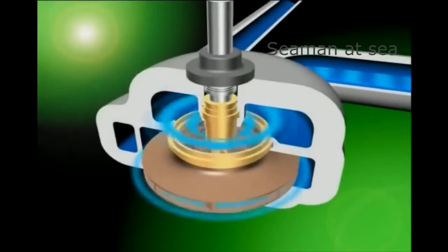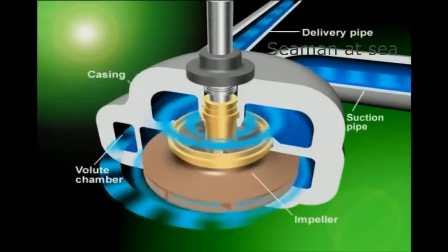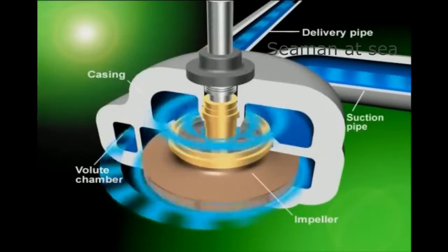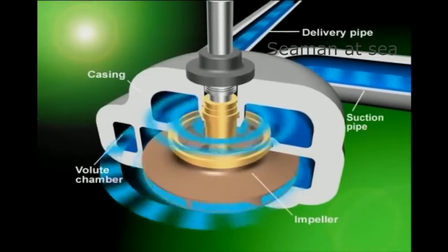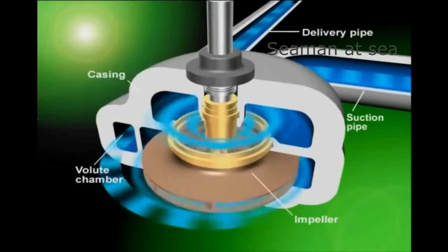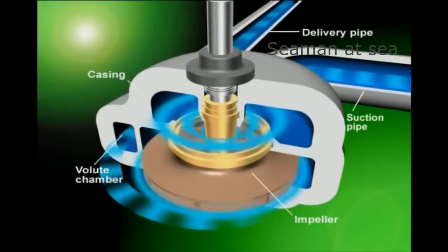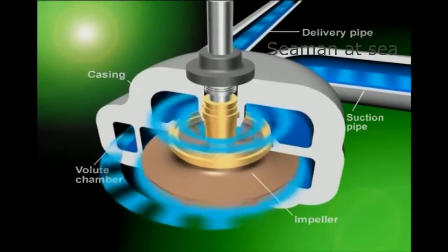With actual pumps, when the impeller is rotated at high speed in a casing filled with water, pressure at the impeller center area drops. Then, pushed by atmospheric pressure, water is allowed to flow into the pump through a suction pipe. The water, splashed by the impeller's centrifugal force, gathers in the volute casing and gains in pressure before flowing out of the delivery pipe.